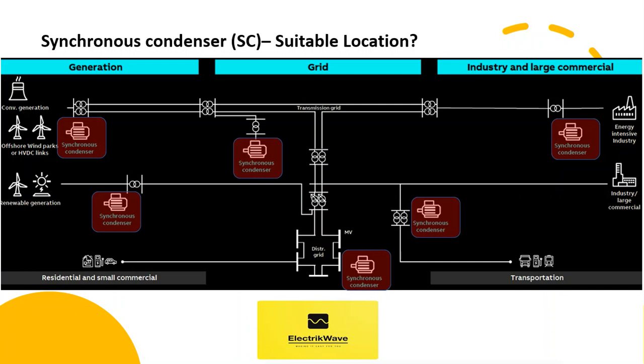For transmission system operators, synchronous condensers mitigate protection problems due to decreased short circuit level, rapid changes in power flow, system stability problems, power system splits due to different inertial levels, and other issues. They can facilitate inertia planning, provide additional short circuit capacity to strengthen the network and remedy voltage collapse during heavy load peaks. SCs can also mitigate transient faults when integrating large wind farms and enable higher system availability through redundancy when multiple units are installed. To reduce the risk of power oscillation, SCs can be remotely deployed in decentralized grids.